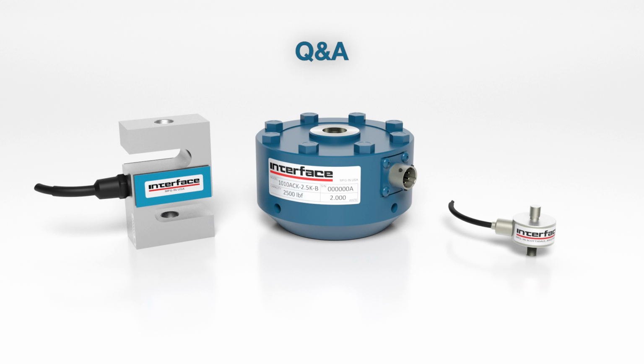Are there any advantages to using bipolar plus or minus 5 volt over 0 to 10 volt? Well, this is going to be, again, a function of instrumentation in the application. If you're looking to measure both directions, then yes, the bipolar would be an advantage. Unipolar, some instrumentation may only function in a 0 to 10 or 0 to 5 environment. At that point, if we were trying to go in both modes, in tension and compression, we would have to be investigating options for a zero offset of some kind, and we do have instrumentation options that I believe we could make work with that scenario.